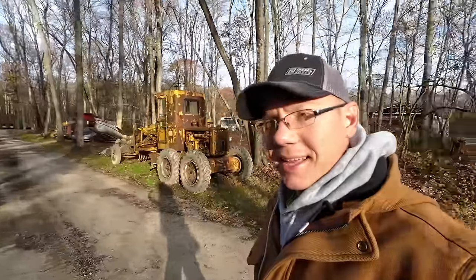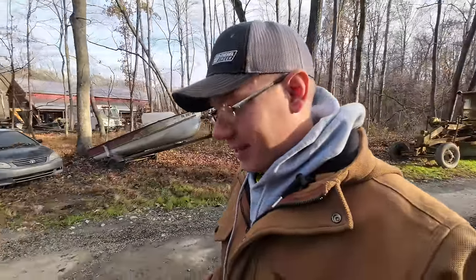If you've never seen this done, it's pretty fascinating. It's kind of a mind blower. You wouldn't think that it works as well as it does, barring any issues like I said, obstructions in the conduit. But we're gonna be pulling the string line through like 600 feet of conduit with nothing but a shopping bag, a string line, and a shop vac.